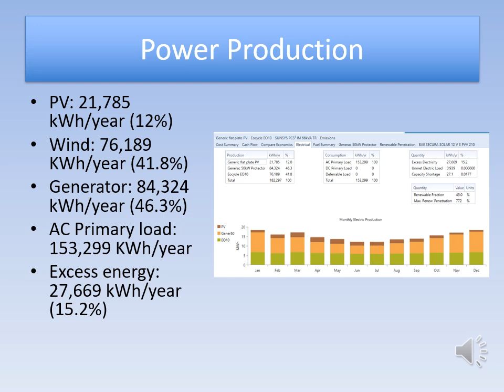For power production, our simulation showed that the hybrid system would produce around 21,785 kilowatt hours a year, which is around 12% of total generation from PV, and from wind turbine we got 76,189 kilowatt hours per year, which is around 41.8%, and the rest of the power we generate from diesel source, which is almost 46.3%. And our AC primary load is around 153,299 kilowatt hour, and we have some excess energy which is around 15%.